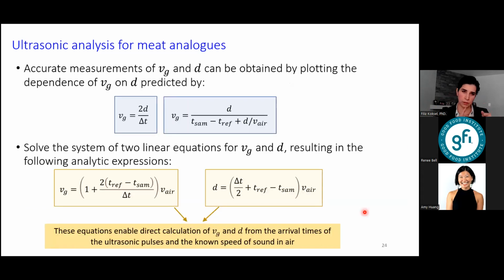But since we didn't want to just stop and measure the extrudate thickness, you could simply plot the dependence of velocity on the thickness of the extrudate. And it just becomes a system of 2 linear equations that you can solve for, and you can get the velocity of sound waves and the thickness of the extrudate that's just based on the time and velocity of sound waves in air. So these 2 equations enable direct calculation of the velocity and the extrudate thickness from the arrival times of the ultrasonic pulses and the known speed of sound in air.